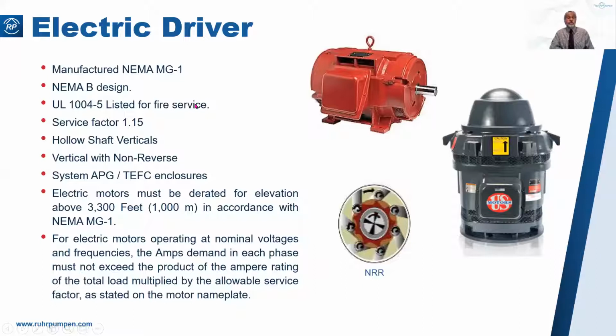Motors should be UL listed. This can be a problem if you are going to send us your motor specifications, which might be for a different type of motor. So if it's not a NEMA MG1, NEMA B design UL listed motor, it might well be that we would have to take exception to listing, for example. Vertical pumps have vertical hollow shaft motors with non-reverse ratchets.